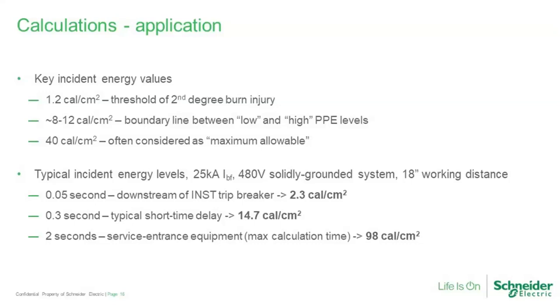In IEEE 1584, there is guidance that in most cases you're okay cutting off calculations at 2 seconds. The idea being that by 2 seconds, hopefully your reactions kick in. You remove yourself from the source of the heat, or in worst cases, a worker might be blown backwards away from the most intense arc flash. But 2 seconds, which might apply at your service entrance equipment, even with those parameters, 25,000 amps, relatively moderate, you're looking at close to 100 calories per centimeter squared. So quite a bit of energy can be available on a real system.